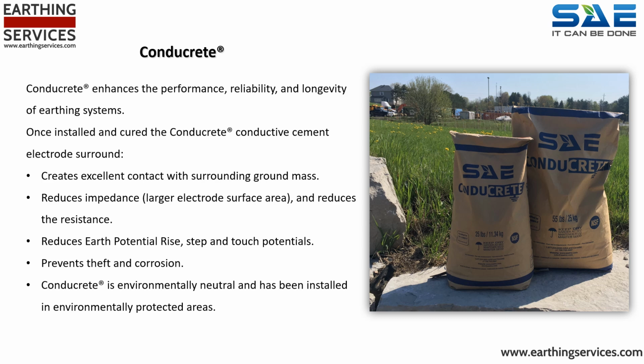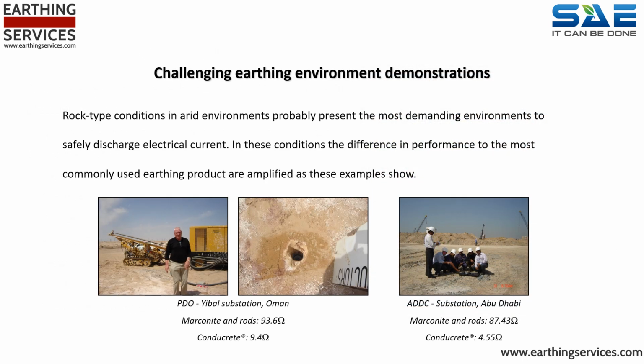Conducrete® has been used to provide an earth on all manner of projects, including deep vertical electrode earthing, horizontal electrode earthing, distribution earthing, transmission earthing, substation earthing, and earthing system retrofits. The more challenging the environment, the greater the disparity in improved performance compared to others in the market.